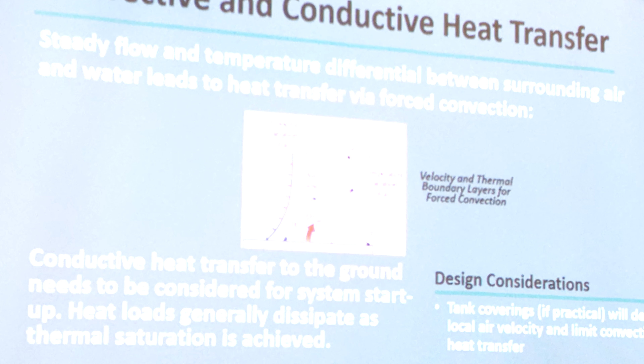However, the convective losses from the surface of the water can be substantial as well. For an indoor facility, what you'd want to consider is your level of air replacement, how much airflow is going through the system. The faster that air is going and the higher the temperature differential between your water and the air, the more heat you can lose or gain into your water through convection. So again, other quick things to keep in mind as you're sizing a system: consider if you can cover or in any way slow down the air local to the tanks. Probably not that possible, but that could substantially limit your convective transfer, and any insulation you can put at the bottom is just going to create a more thermally isolated system.